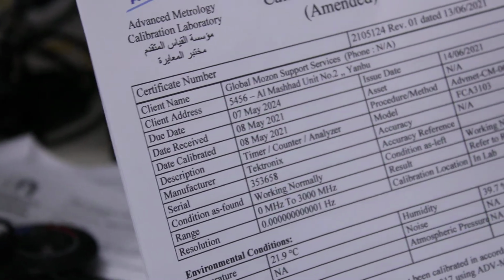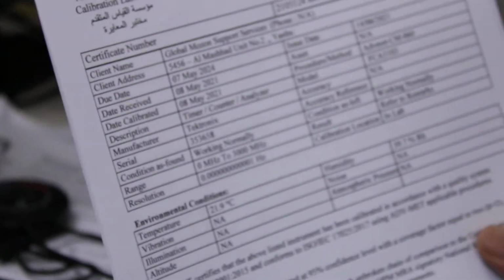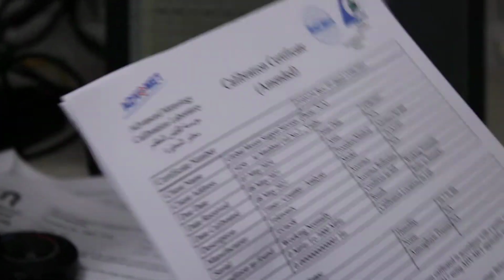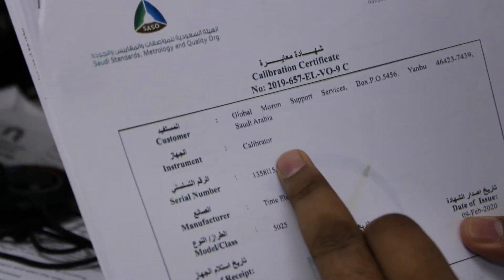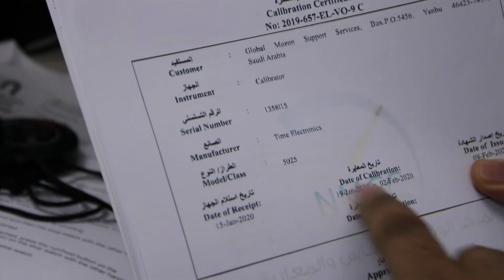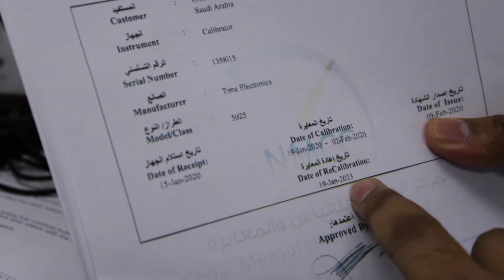For both calibrations we have used our reference certificate for the timer counter analyzer. This one was calibrated on 8 May 2021 and is valid until 7 May 2024, and they calibrated the frequency, because we also test only frequency. And for the generator frequency source, we have our calibration certificate for the calibrator MFC Time Electronics 5025. This one is valid until 19 January 2023. And for quality control checks we have done ILC/PT.